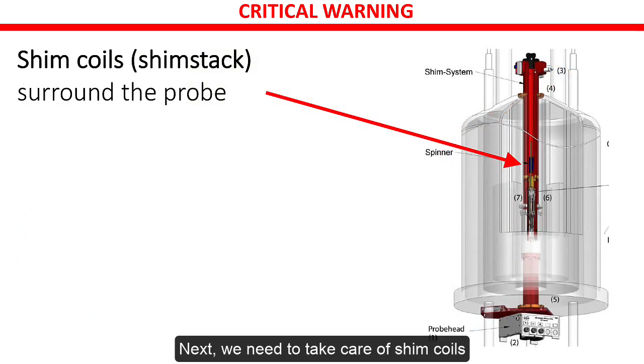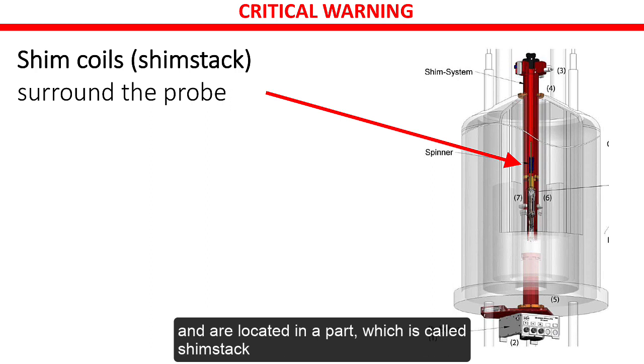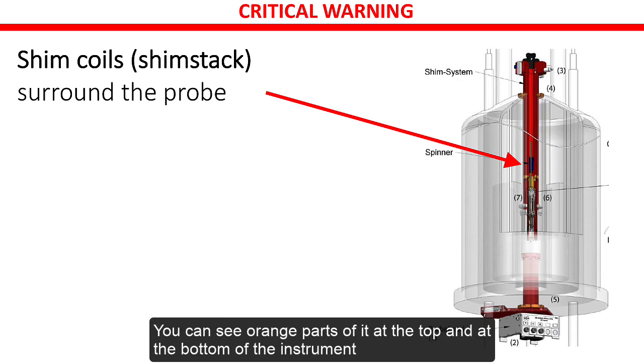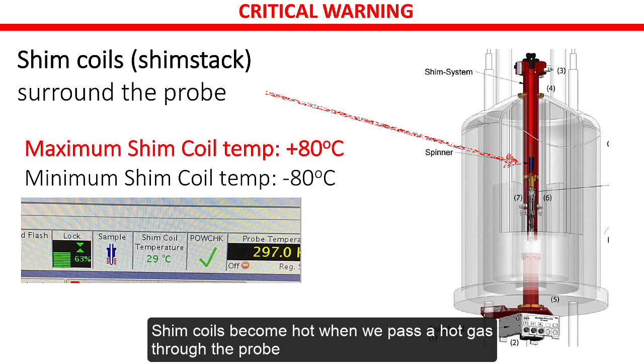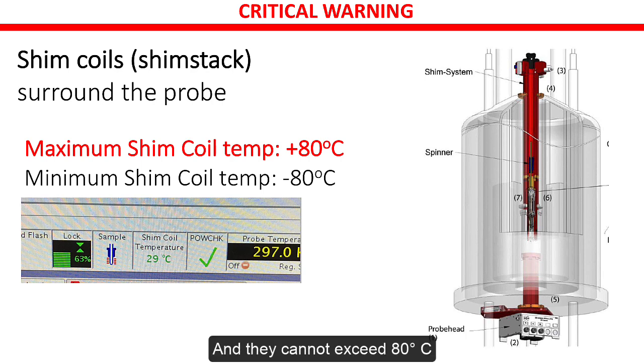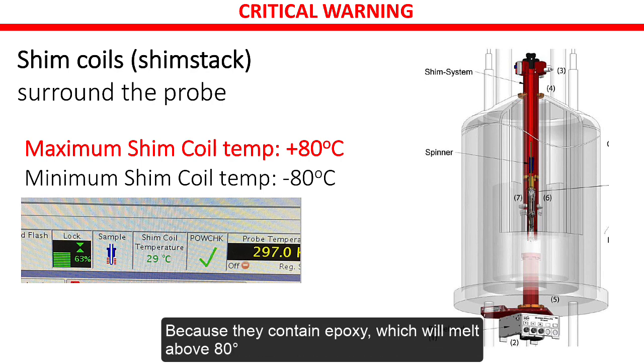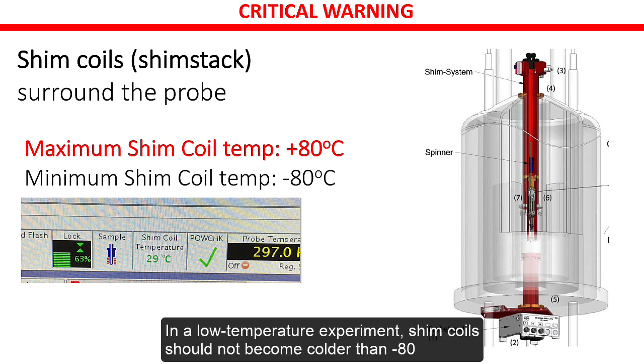Next, we need to take care about shim coils. Shim coils surround the probe head and are located in a part which is called the shimstack, which passes through the bore of a magnet, and you can see the orange part of it on the top and on the bottom of the instrument. Shim coils become hot when we pass a hot gas through the probe, and they cannot exceed 80 degrees C because they contain epoxy, which will melt above 80 degrees. In a low temperature experiment, shim coils should not become colder than minus 80.